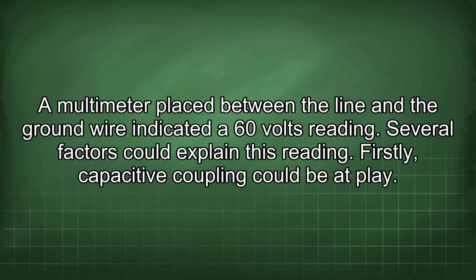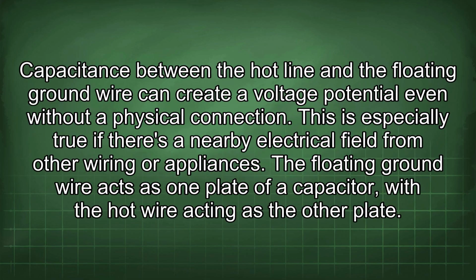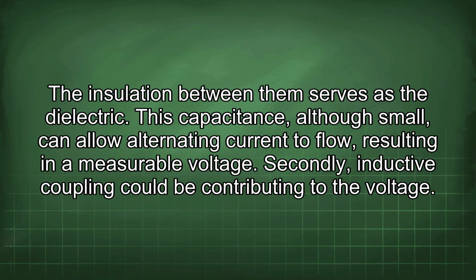Firstly, capacitive coupling could be at play. Capacitance between the hot line and the floating ground wire can create a voltage potential even without the physical connection. This is especially true if there's a nearby electrical field from other wiring or appliances. The floating ground wire acts as one plate of a capacitor, with the hot wire acting as the other plate. The insulation between them serves as a dielectric. This capacitance, although small, can allow alternating current to flow, resulting in a measurable voltage.